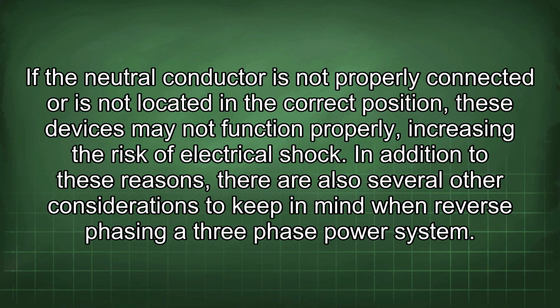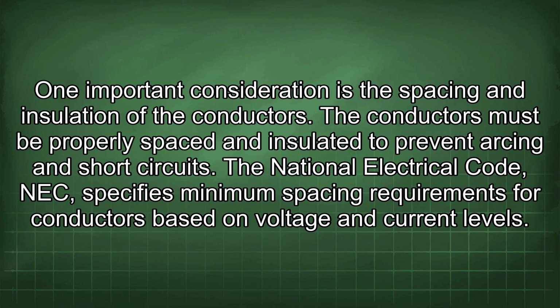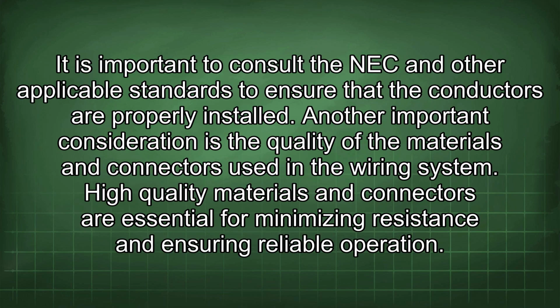In addition to these reasons, there are also several other considerations to keep in mind when reverse phasing a three-phase power system. One important consideration is the spacing and insulation of the conductors. The conductors must be properly spaced and insulated to prevent arcing and short circuits. The National Electrical Code, NEC, specifies minimum spacing requirements for conductors based on voltage and current levels. It is important to consult the NEC and other applicable standards to ensure that the conductors are properly installed.